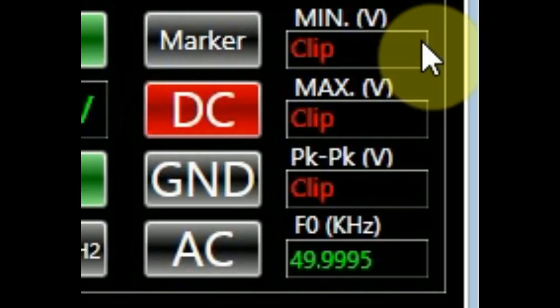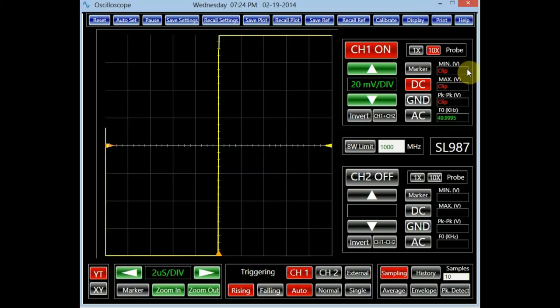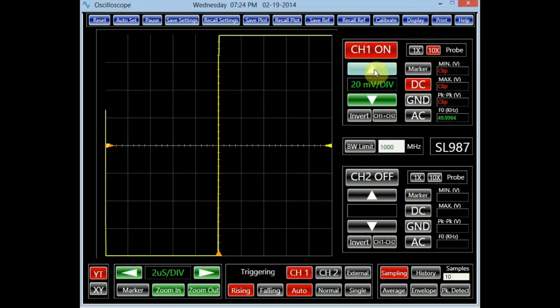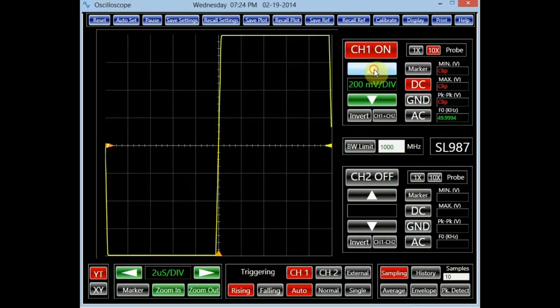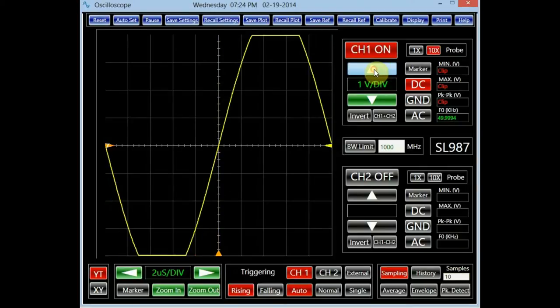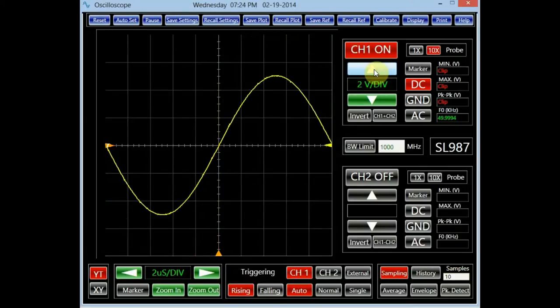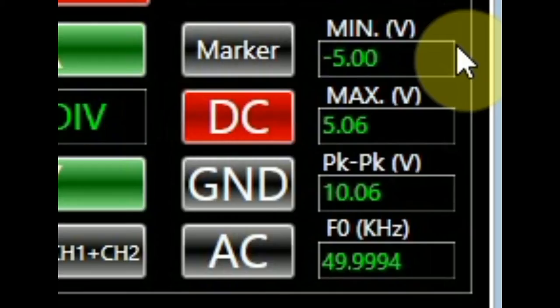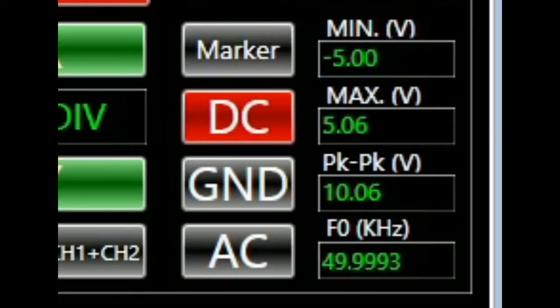When clipping occurs, the data is no longer valid. The data information panel highlights this condition in red. Once the voltage setting is adjusted for channel 1 such that clipping does not occur, the maximum voltage of the signal, its minimum, its peak-to-peak value, and its frequency are accurately displayed in the corresponding panels.